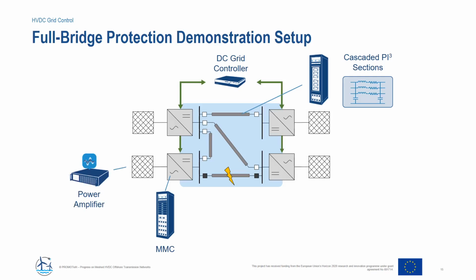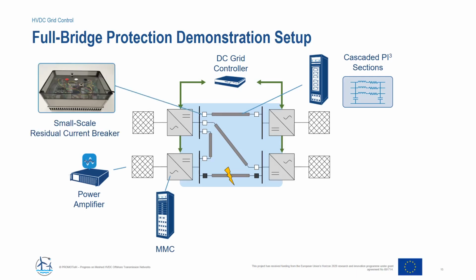The AC grids are represented using power amplifiers, and for these tests, the power amplifiers are only set into voltage source mode because the focus of the demonstration lies within the DC grid. For power hardware in the loop simulations, for example, there we would then use a simulation of an embedded AC grid. The fault separation units, also called residual current breakers, are small-scale breakers designed by KTH, which have been applied here, and these are only allowed to interrupt once the current is relatively low, so below, I think, 10% around its nominal current.